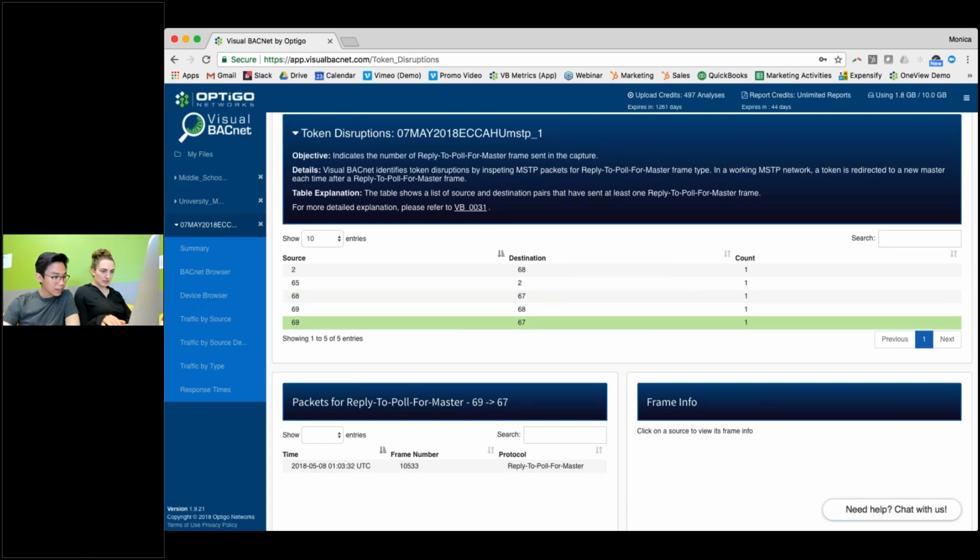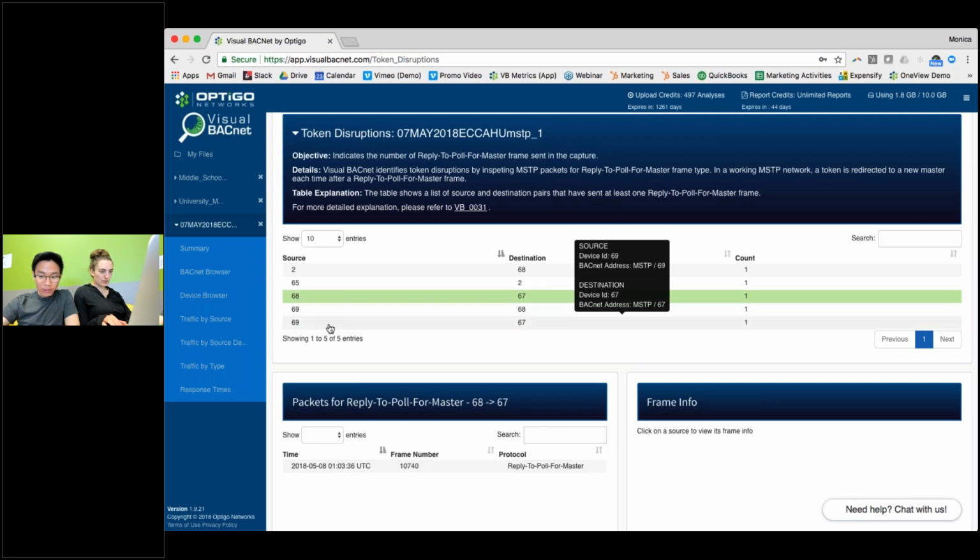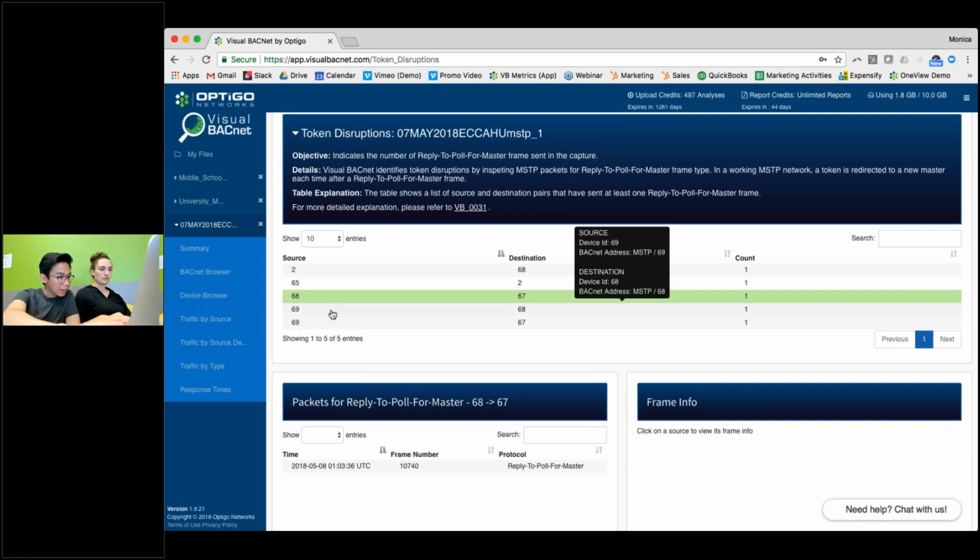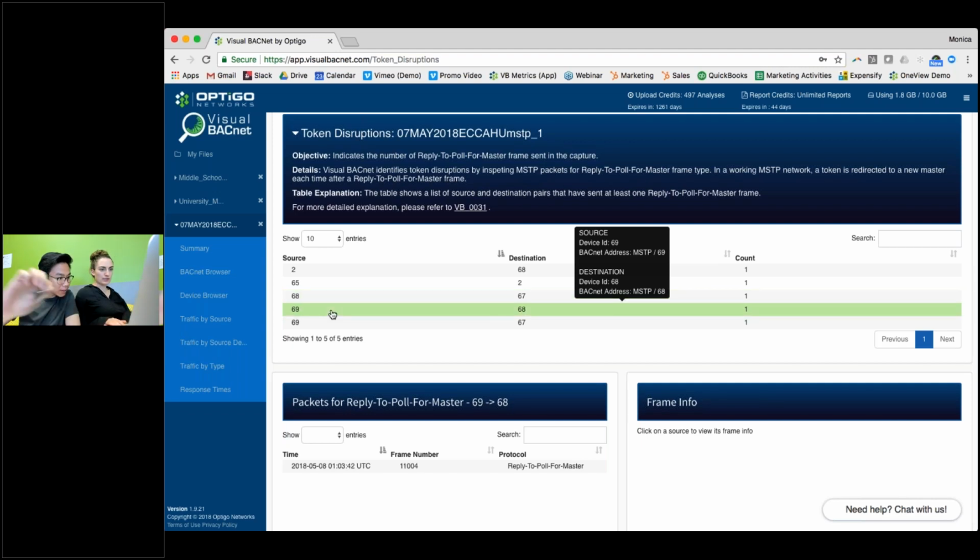69 to 67, so within the same second. Oh, no. 3:32, 4 seconds before, 68 went offline. 67 said, who's the next master? And 69 said, I am. Then 4 seconds later, it went back to 67 after 50 trips probably. So it did 50 trips, and then on its 50th trip, it polled again, and 68 said, yeah, I'm the master, and came back online. And then the same for this one. So this is a lot later, 3:42.